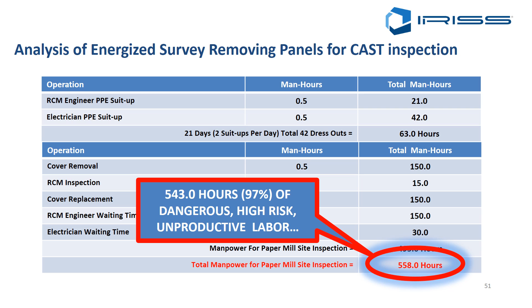Now, if we look at the inspection with electrical maintenance safety devices completed, obviously because there's no panel removal, there's no suit up time - all of that PPE time goes away. You do the inspection in your everyday PPE because you leave the panel in an enclosed and guarded condition. That way you haven't got to increase your PPE. Obviously no cover removal or replacement.